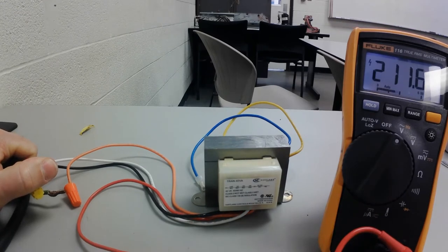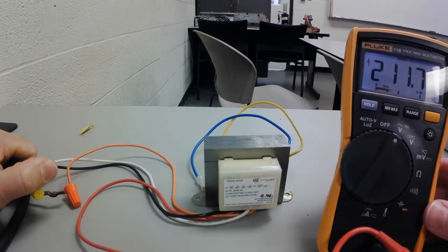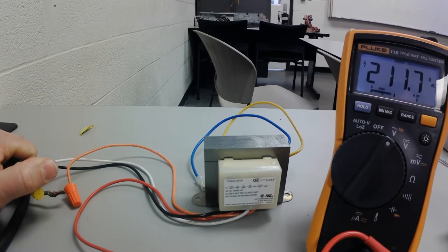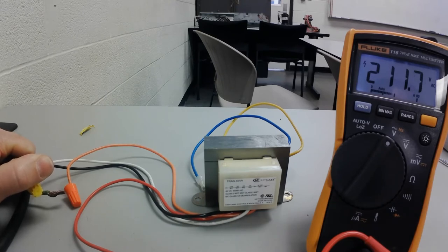That's 211 volts out of 120 volts out of the wall. How did I get this voltage? It's because we tapped into a different portion of the winding. Okay, and I'll show you that again in just a second. So that is my 208 terminal. Let's look at the 240.